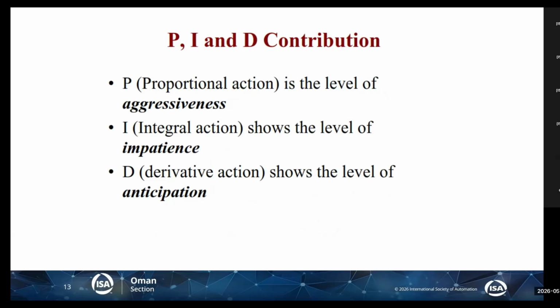So what are P, I, and D? P is the proportional action. Proportional action is the level of aggressiveness: how aggressive, how fast do you want your controller to be? So if I want my controller to be fast acting, I should have more proportional action. In some DCS, like Foxboro and maybe Yokogawa, we have something called proportional band. It's nothing other than 100 divided by the proportional, so PB is 100 divided by P. Of course, we always want the controller to be as fast as possible, but sometimes you cannot make it fast due to the sensitivity of the loop. The loop is very sensitive, and you cannot make it fast.